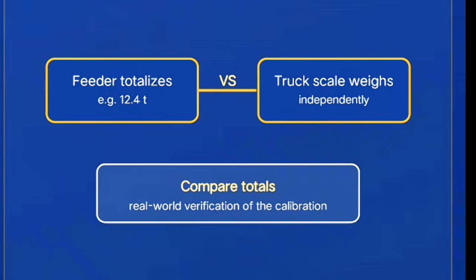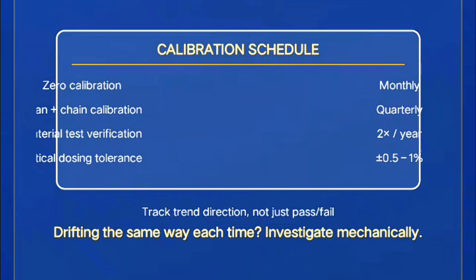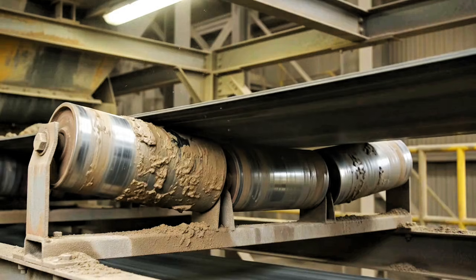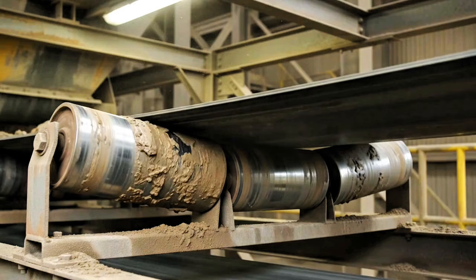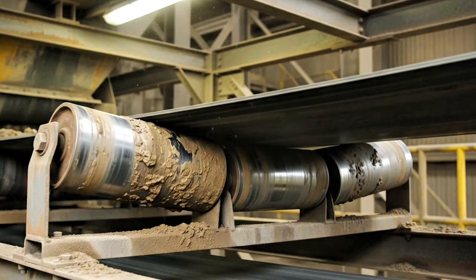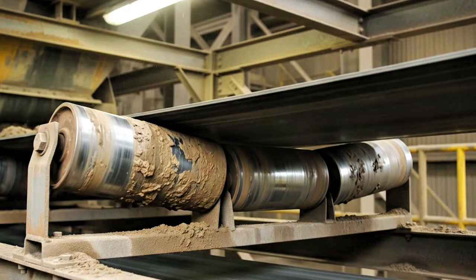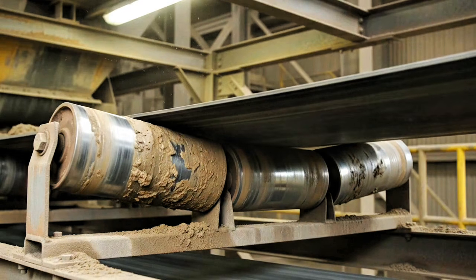How often should you calibrate? As a baseline, I run zero calibration monthly, span and chain calibration quarterly, and a full material test verification twice a year, but adjust that based on your feeder's duty, the abrasiveness of your material, and what your own trend data tells you. A feeder running raw coal with heavy dust and moisture variation needs more frequent attention than one running dry, consistent raw meal.